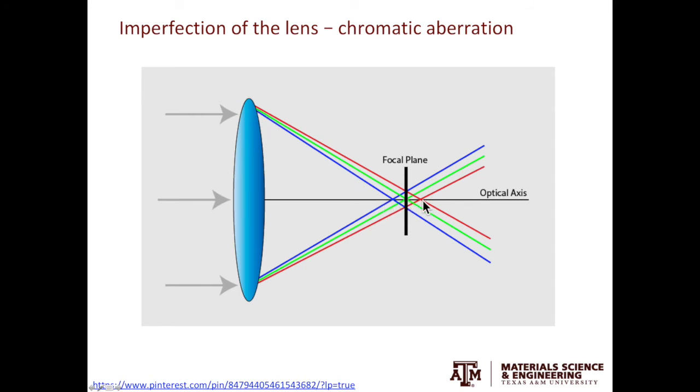In TEM, when the electron beam leaves the electron source, there is an energy spread and that leads to the chromatic aberration. The lack of the ability to focus all the beam to a single point leads to the smearing of the image. If you recall one of the previous videos, the energy spread from the electron source is the temporal coherency of the electron source.